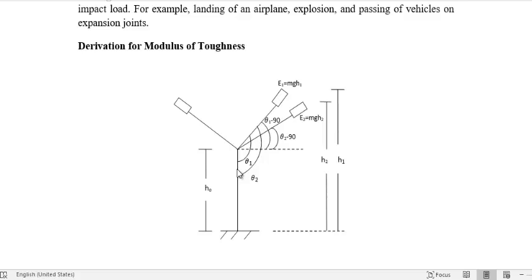And at every rotation we will note down the angle of rotation of the hammer. The scale that is connected with the instrument measures the angle with respect to this vertical. So the angle that will be attained in the free run, we can call theta1.